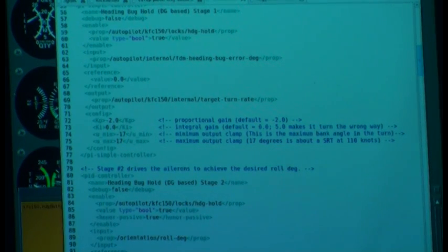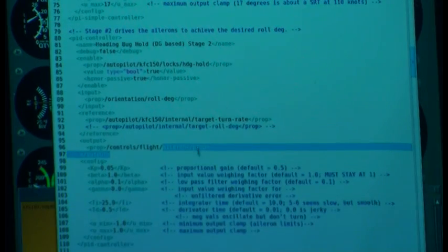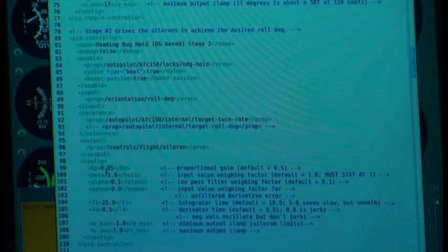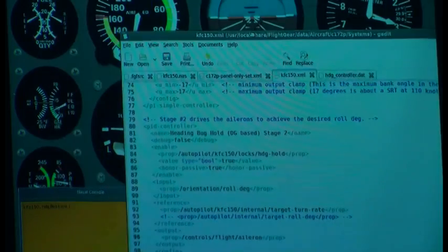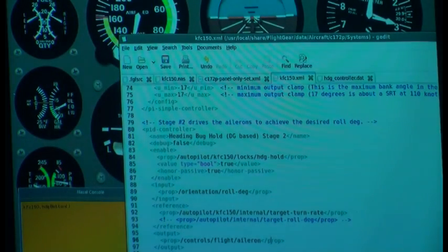So it's a cascading controller, just like in the paper mill, where they'd use it for pneumatic controls. It's a PID controller, okay, proportional integral derivative. You don't have to know calculus, you just have to understand a little bit about it. So you can tweak any of these values right here in the config section, and it will change it all. For example, let's check this one, and let's say that it's 0.05, let's have fun. Let's make it 0.5, so it's a factor of 10.